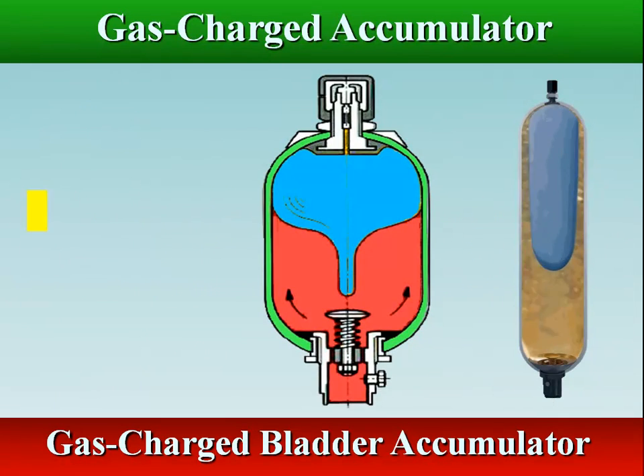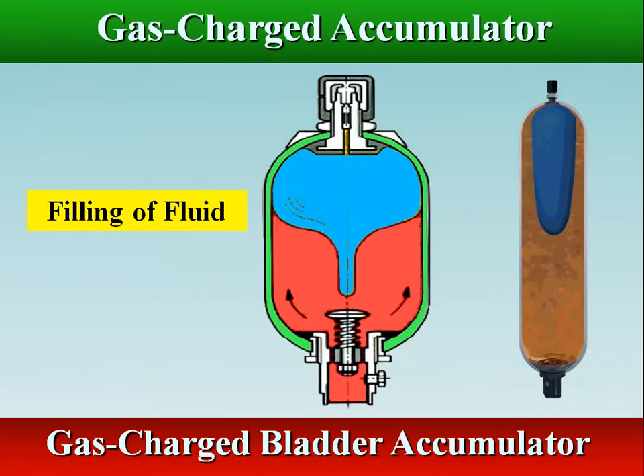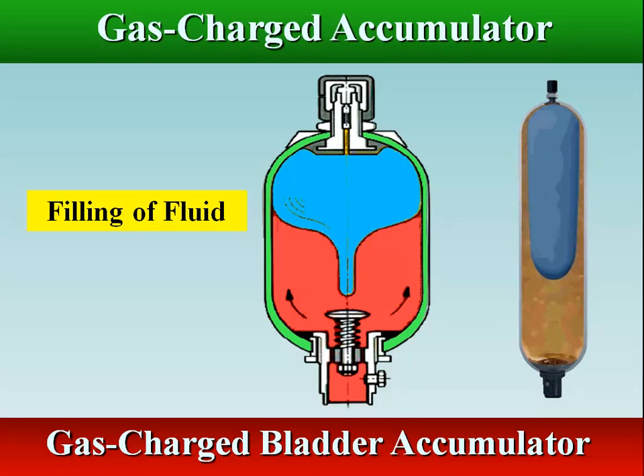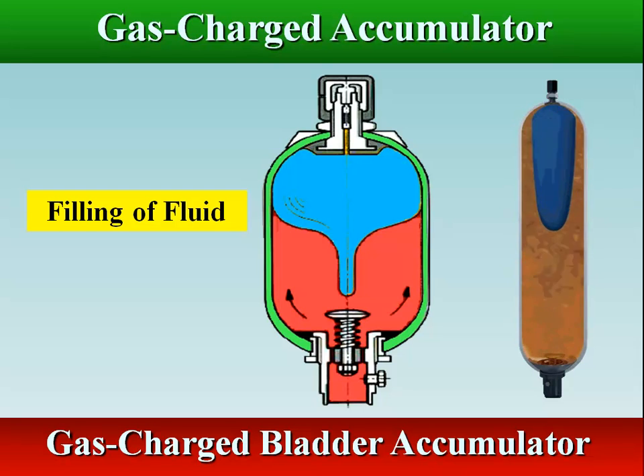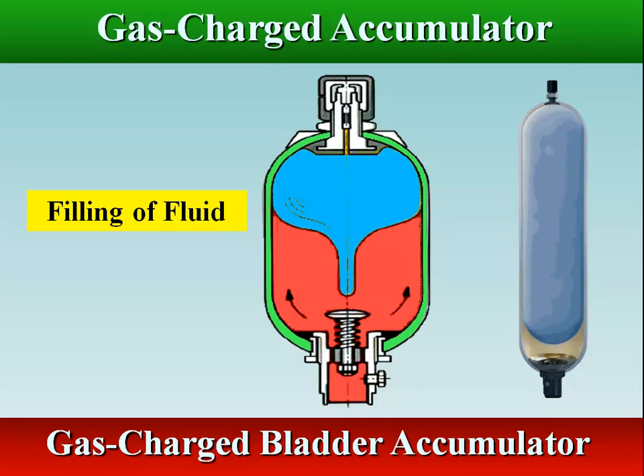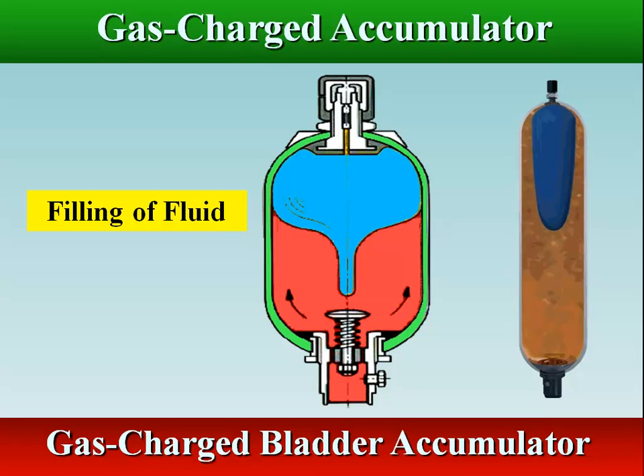When the hydraulic pressure external to the accumulator is higher than the pressure inside the accumulator, oil from the hydraulic circuit is forced into the accumulator, compressing the gas and thereby storing energy in the compressed gas, and also storing a reserve volume of oil around the bladder.